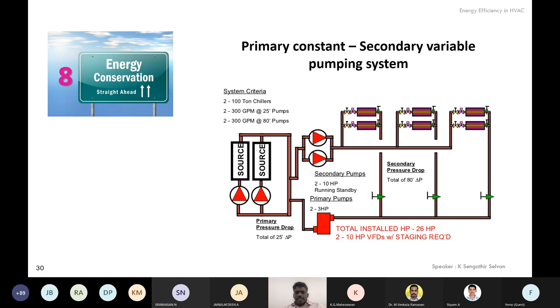So here we have these pumps at variable speed, and this primary pump on the left side will be at constant speed. We have broken that hydronic system, and we have a small hydronic decoupler line also. And as I told you, nowadays the chillers are available with a minimum flow of up to 60%. So what we are trying to do is add VFD to the primary chilled water pumps, so that they will be modulated to meet the minimum flow requirement of the source side. So that is called the primary variable system. That is energy conservation measure number 9.